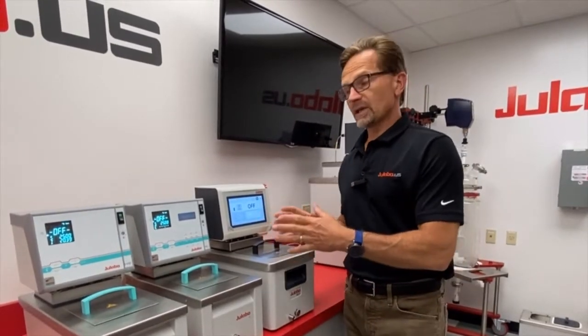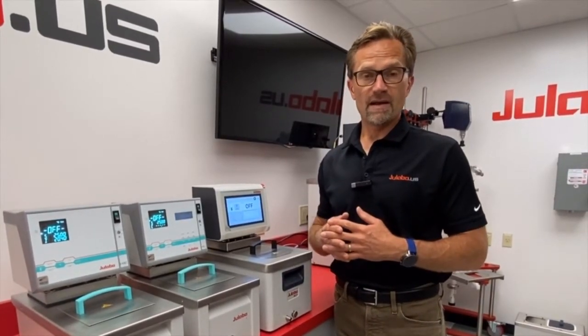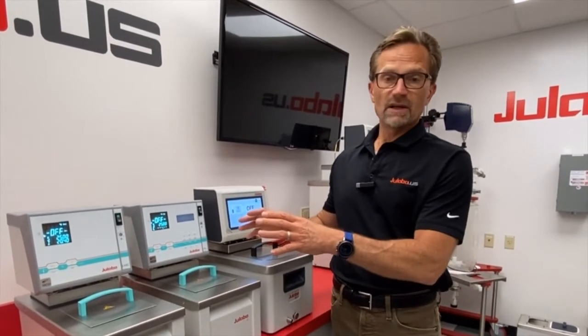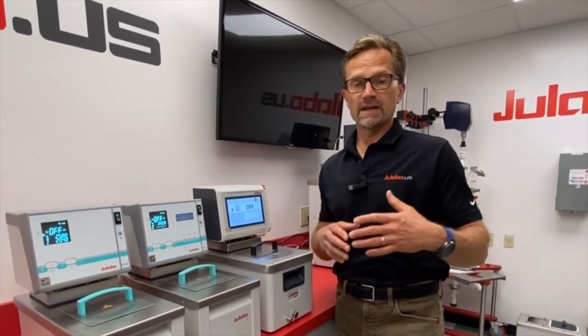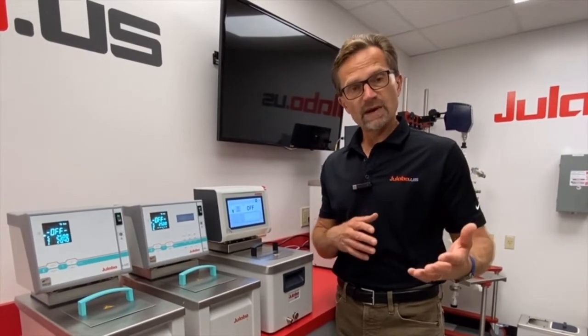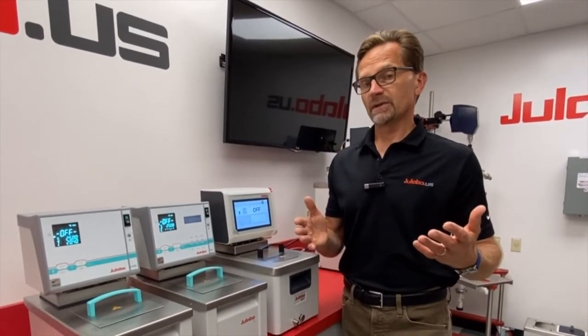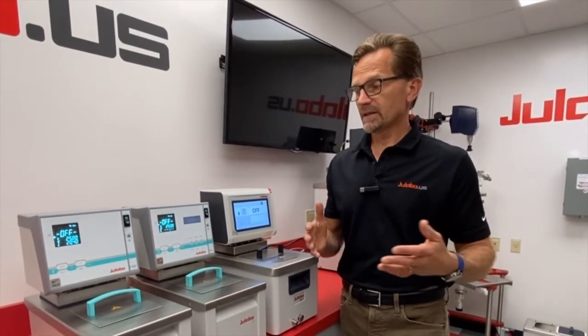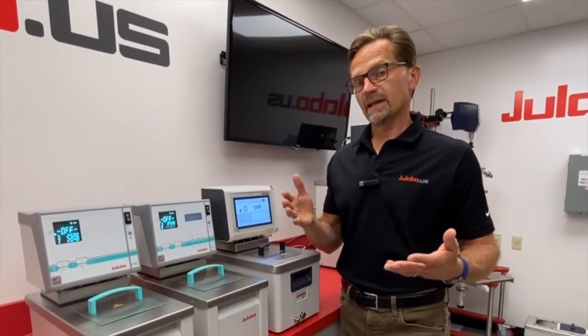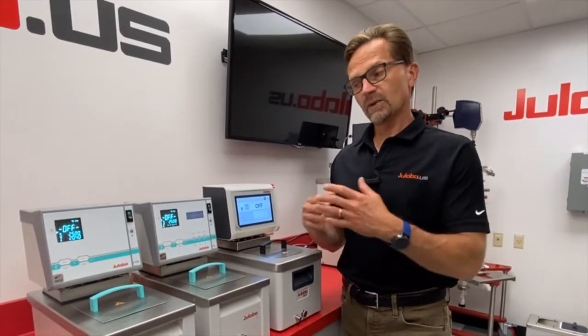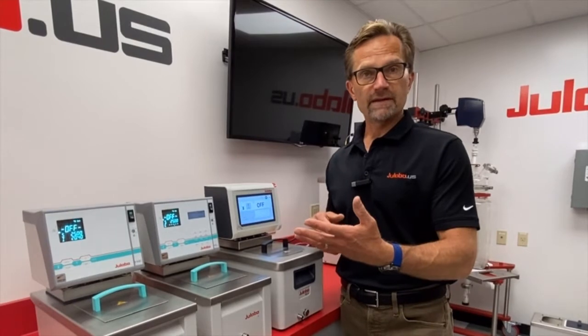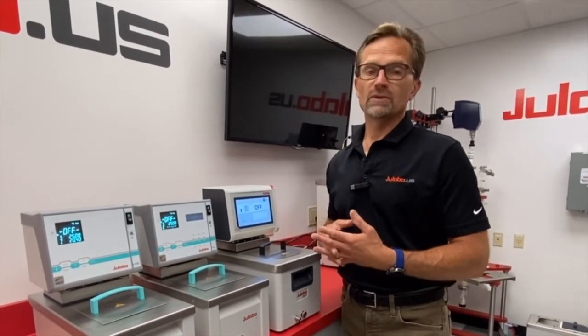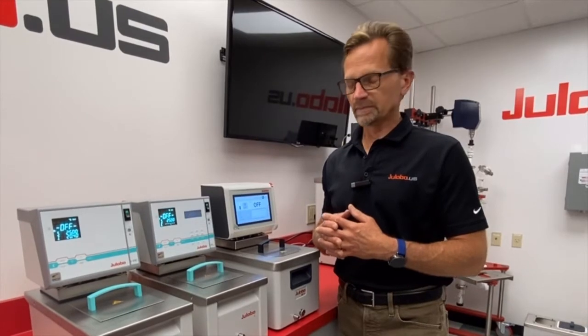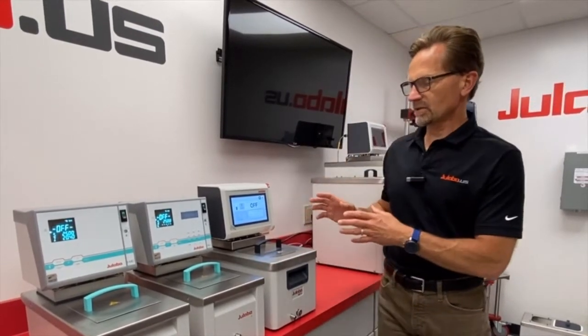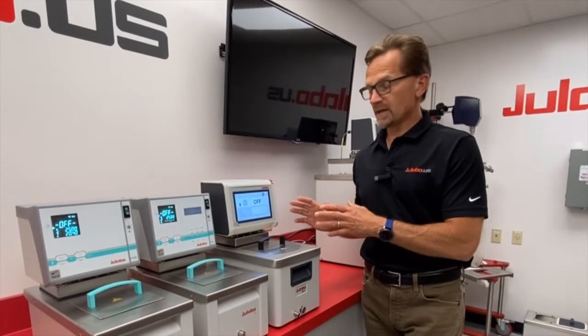So these circulators can also come in combinations with refrigeration units for refrigerated heating circulator combinations. The HE and the HL can come paired with refrigeration systems enabling a temperature range starting at -28 with an upper temperature limit of 200 degrees C in refrigerated heating combinations, with the largest unit going down to -50, again with the upper limit up to 200 degrees C. The cooling power ranges from the smallest one having 350 watts cooling power up to 900 watts cooling power in the largest one.